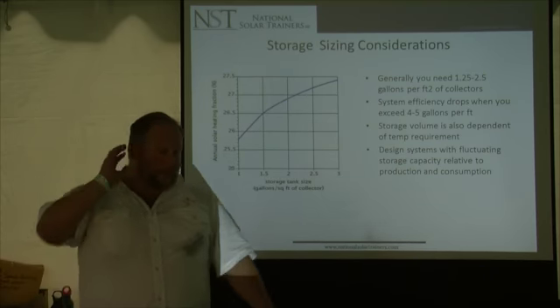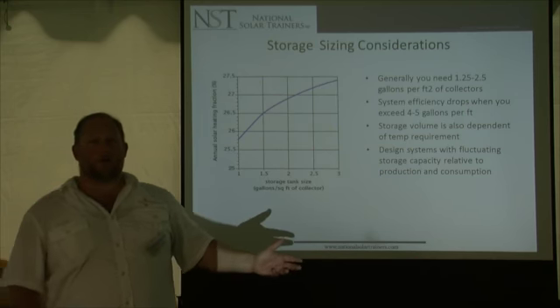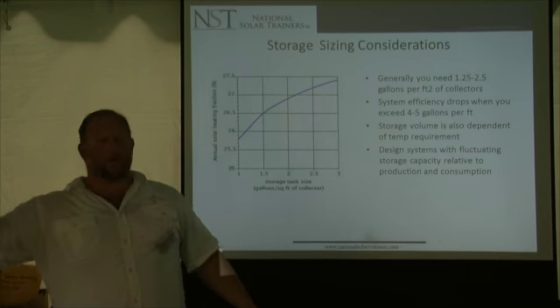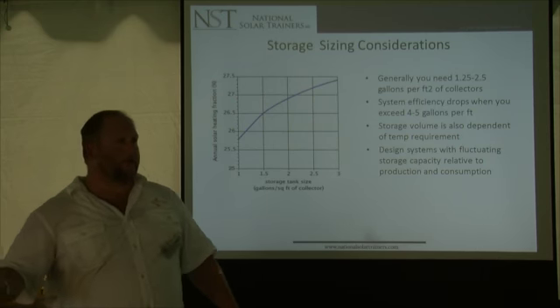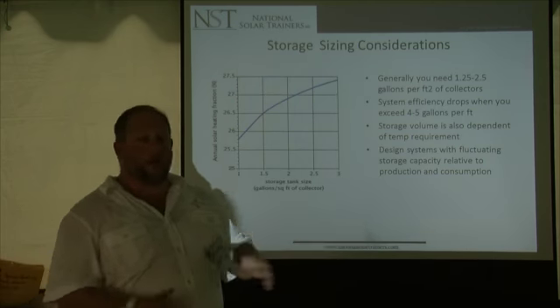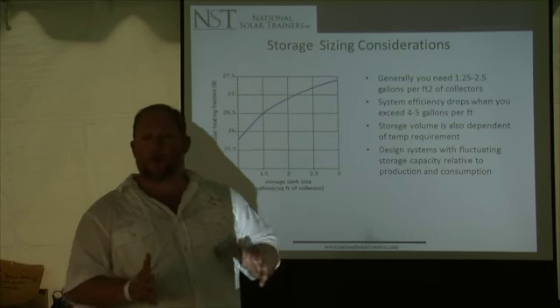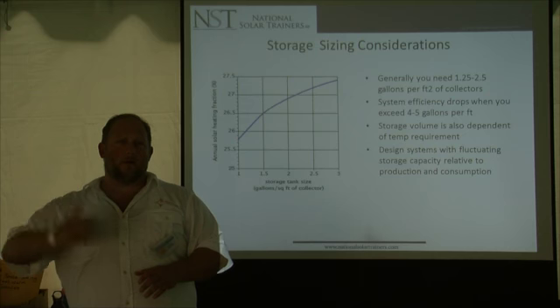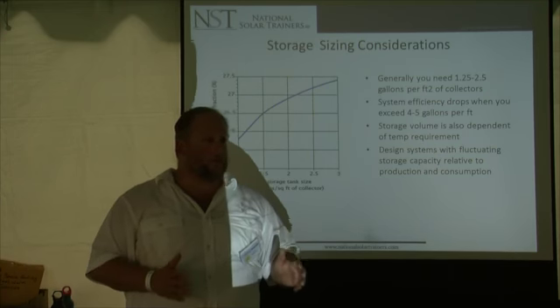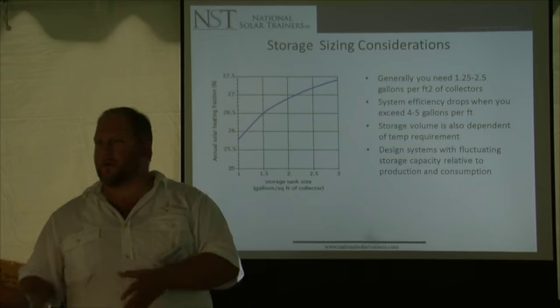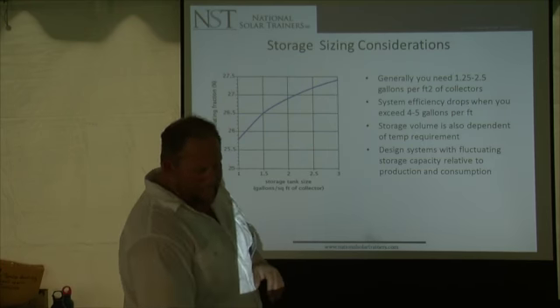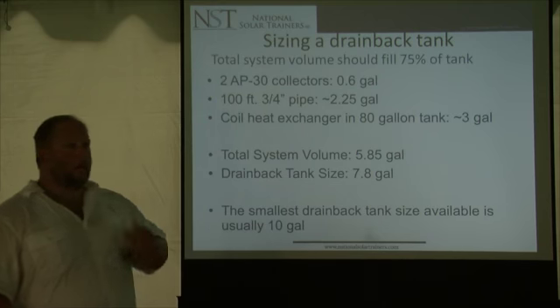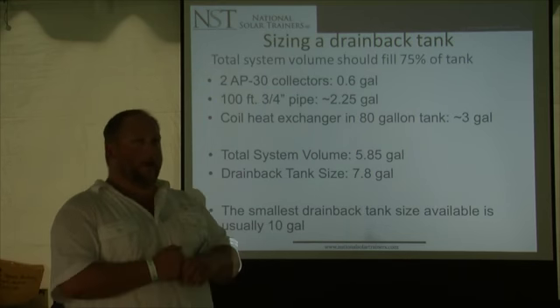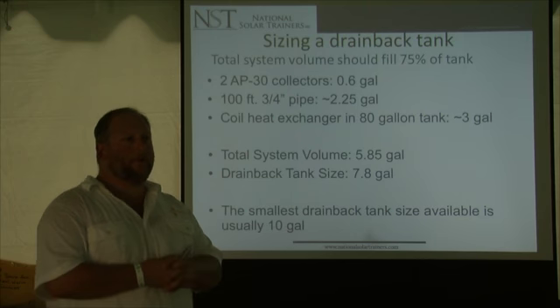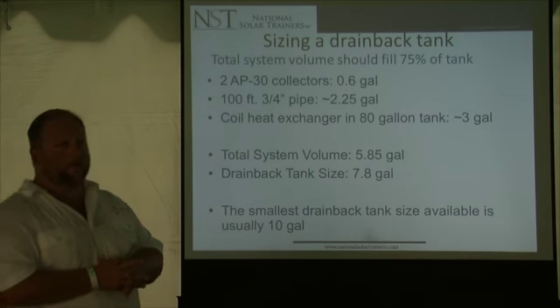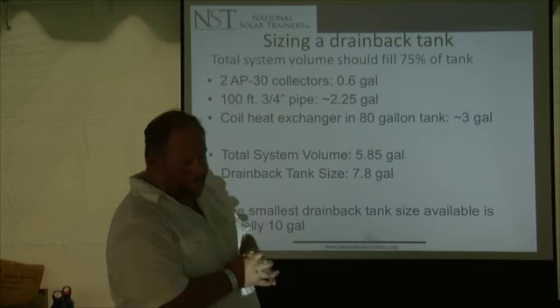Storage sizing considerations: anywhere from 1 gallon per square foot to 2 or even 3 gallons per square foot, depending where you live. Southern California, they can have 3 gallons of storage per square foot of collector. Here, we're better off at about 2. 2 gallons of storage per square foot of collector, right? You're talking about domestic hot water now? Yes. Yeah, there's really no good rules of thumb for heating in terms of storage. It's too complicated. Okay?